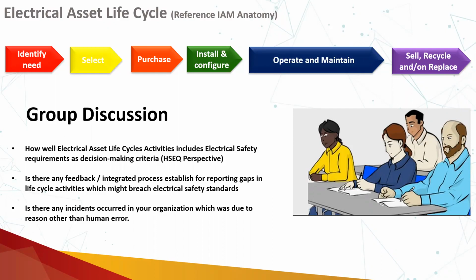I remember when I was working with one company, we had a large number of rotary type switchgear. From field operation, they provided feedback that during operation of these rotary switchgear there were chances of arcing and flashover, because they had aged and become old, and there was some alignment issue. If you were not operating that particular switchgear in a particular manner, there were chances of arcing over or flashover.